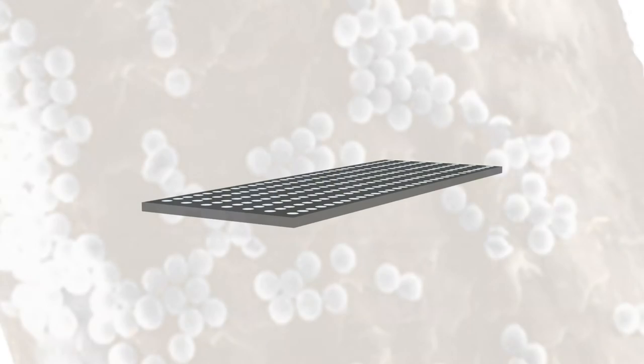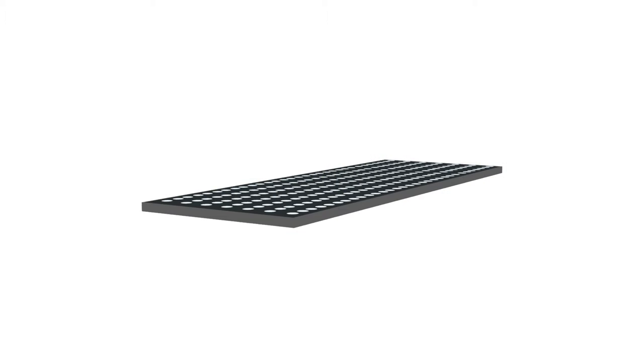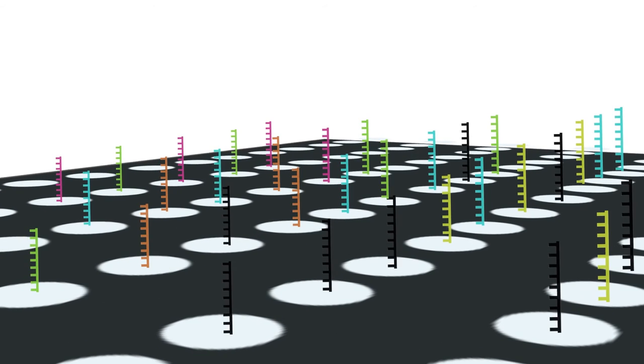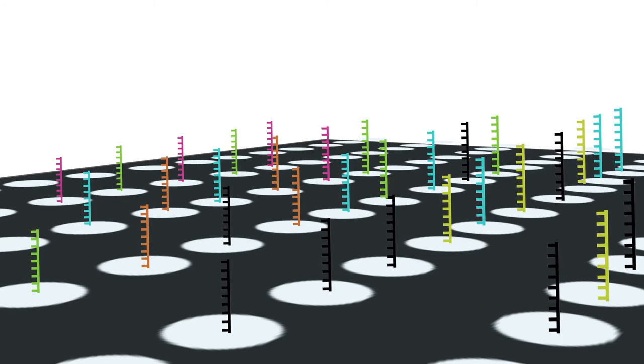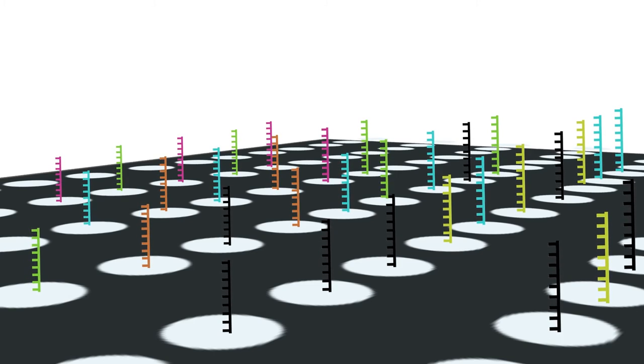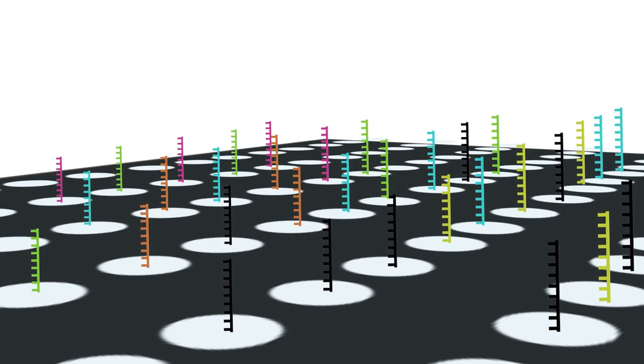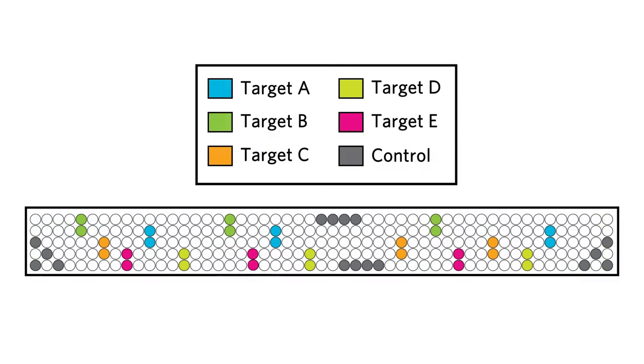Nanogrid Technology utilizes slides covered in spots, called nanogrids. These spots contain strands of DNA complementary to the various targets of interest. The type and layout of the DNA spots will vary depending on the assay. Each spot on the grid contains DNA for a specific target or control nucleic acid.